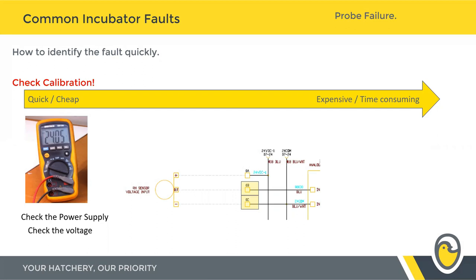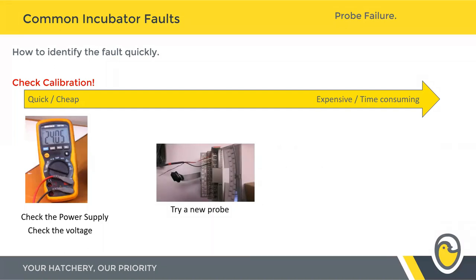Next, check the voltage coming into the PLC. For a humidity sensor, if you're seeing 6.8 volts into the PLC, the screen should show 68% humidity — if that's not what you're seeing, there's either a calibration offset or the input module is faulty. Straight away you can narrow down the fault to being either the humidity probe or the input module. For measuring voltage, check across the signal terminal from the RH sensor compared to your zero volts terminal. For PT100 probes wired to an RTD module, try a new probe — does the value on screen then revert to a correct value? Or swap the probe wiring to a separate input configured for the same type and see whether the fault follows the wiring or stays on the card.